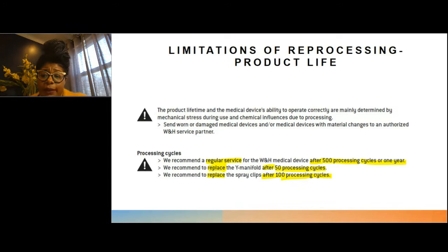In this excerpt for this particular handpiece, the manufacturer recommends regular servicing of that handpiece after 500 processing cycles or a year, whichever comes first. So if you're a very busy practice and that handpiece is being used a lot, you have to develop a tracking system in order to meet this requirement from the manufacturer. There's also a recommendation to replace the Y manifold after 50 processing cycles, and the spray clips after 100 processing cycles.